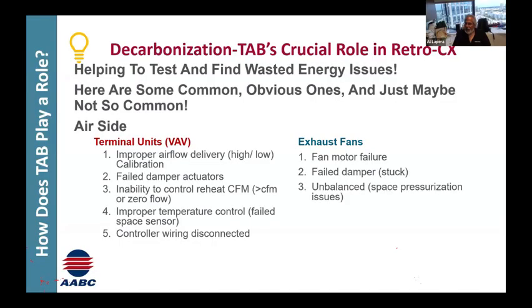Well, one thing you hit on here that's a personal pet peeve of mine is improper airflow and calibration. The reason I say it's a pet peeve is because our control brothers, I don't care the manufacturer, they all say the same thing, that their boxes are auto calibrating. And I tell them, why are you lying to the owner? Because they believe you more than they believe me, because you're the guy that knows. And they go, but I'm not lying.